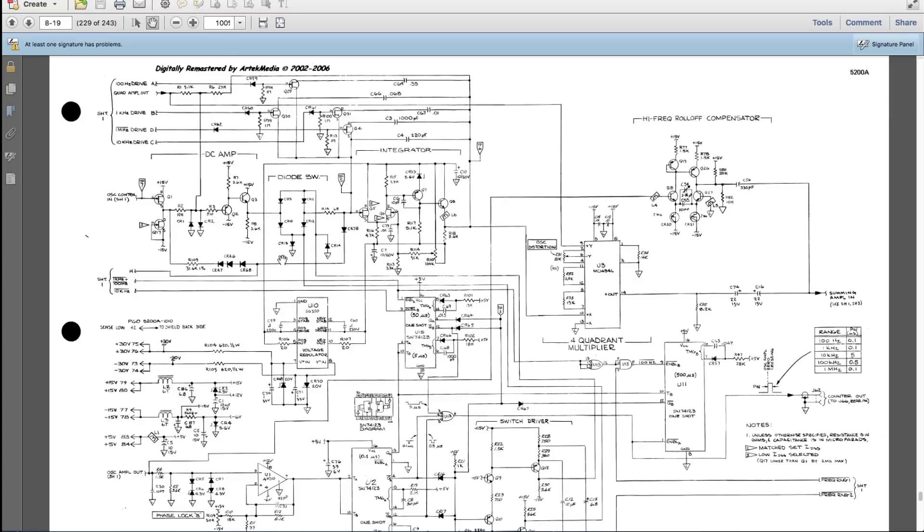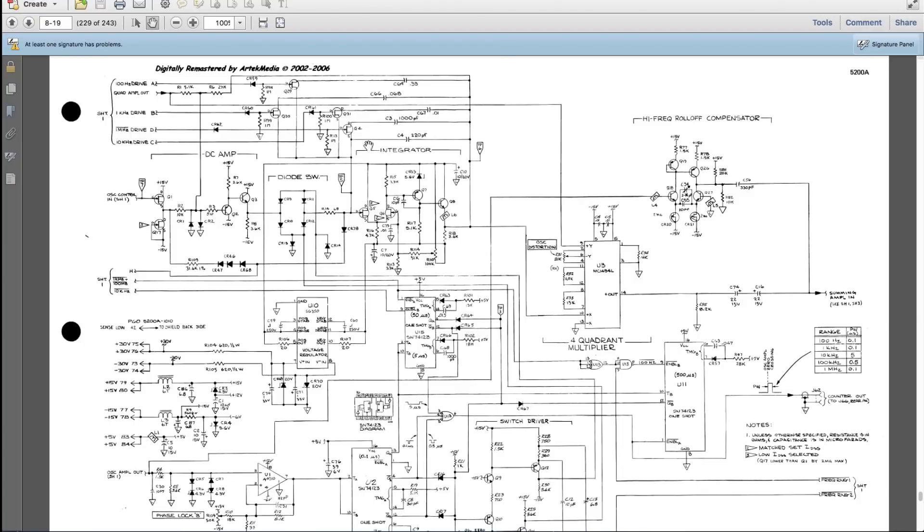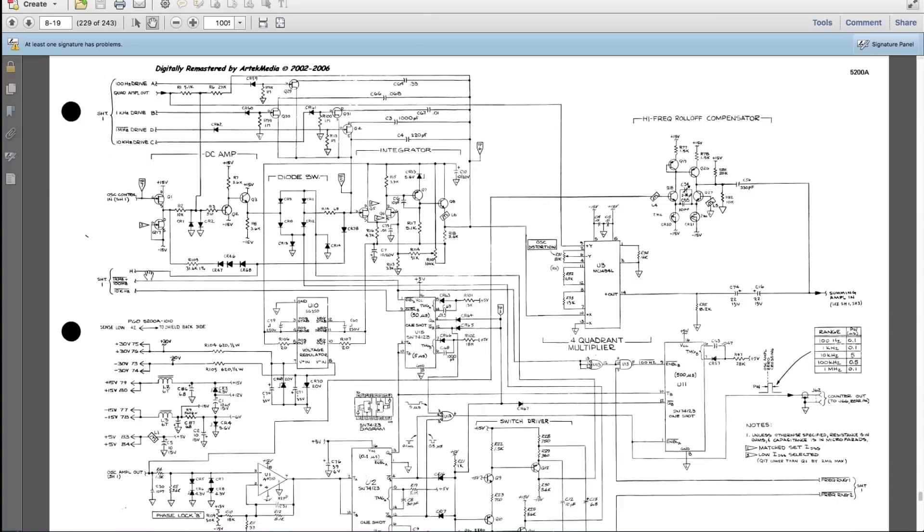So oscillator control in is a level control. I did find some faults. I think I replaced some capacitors somewhere in this part of the circuit. Over here. I think I replaced these caps here. So there was an issue with this particular board and I'm suspicious of this circuit here. I think something in here isn't right. So this is supposed to come out of this device here, go to the amplifier, feed through the amplifier, come back and go across this stuff here. So it's all amplifying DC amps and stuff here as well. So this is supposed to be providing some amplification and it's probably affecting the oscillator.